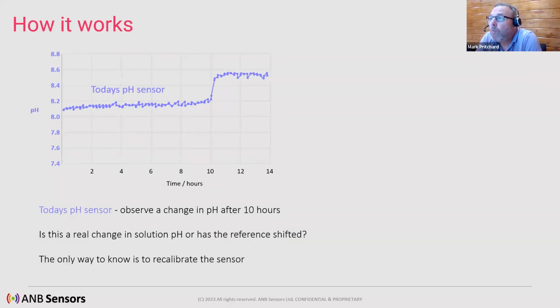Have a quick look to see how the technology works, and I'm sure that everyone on the call here will be aware of a pH sensor that's available today, a glass-based sensor. It needs to be calibrated, and the minute you put it in the liquid or the source for the sensing, it starts to drift. If you see a change in the pH, you're never quite sure, is that a drift or is that an actual change in the pH?